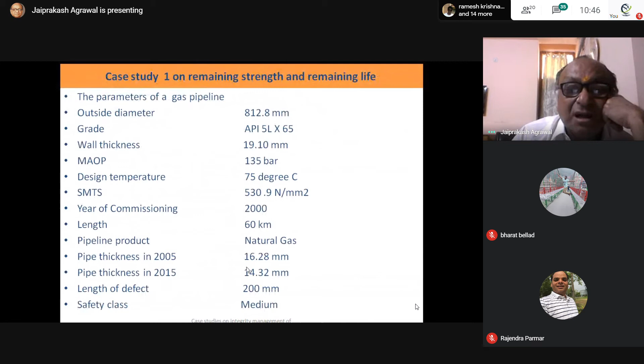That means the corrosion rate is high, because it should be maximum up to 5 mils per year, but it is 12.2 mils per year, so it is in a higher zone. Now you have to calculate the critical pressure. So this is the formula I have told you. Now you calculate d by t.